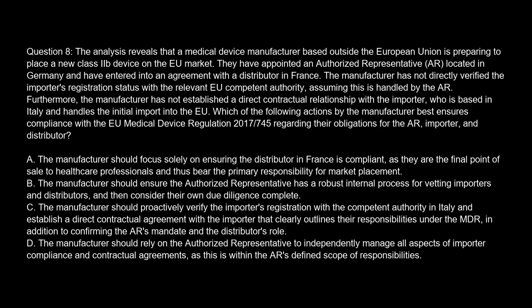Question 8. The analysis reveals that a medical device manufacturer based outside the European Union is preparing to place a new Class IIb device on the EU market. They have appointed an authorized representative, AR, located in Germany, and have entered into an agreement with a distributor in France. The manufacturer has not directly verified the importer's registration status with the relevant EU competent authority, assuming this is handled by the AR. Furthermore, the manufacturer has not established a direct contractual relationship with the importer, who is based in Italy and handles the initial import into the EU.